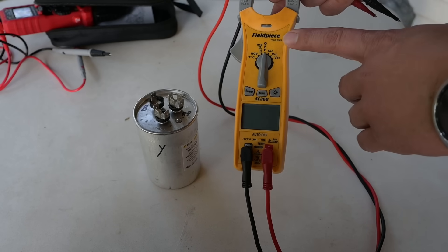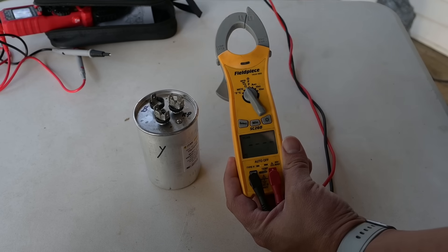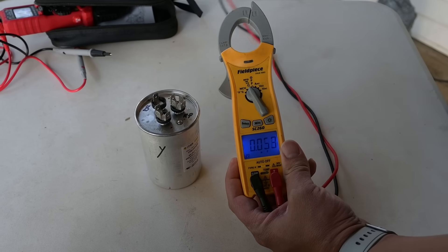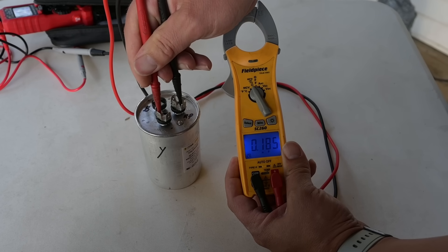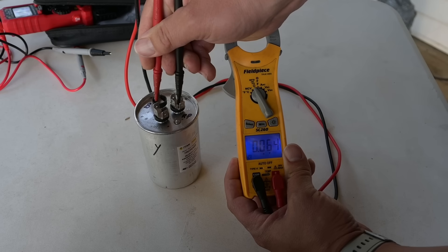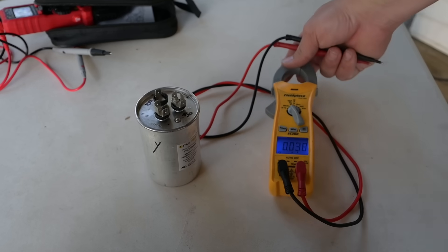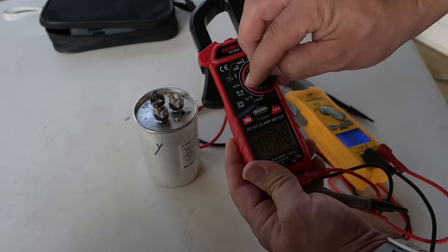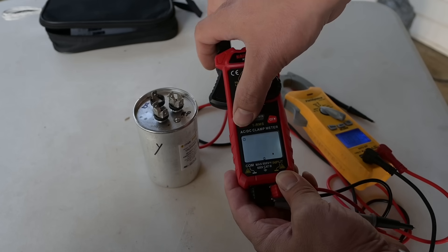Let's test our capacitor. We're going to use our Field Piece SC-260 — a great HVAC troubleshooting electric meter. We hit the select button until it says uF, and now we'll test from our common terminal to the HERM. If this was a good capacitor we'd be getting close to 45 — we're getting zero. And over to the fan we should be getting 5 — we're also getting zero. So definitely a bad capacitor. That's great news; that means most likely this is going to be the only thing we have to replace.